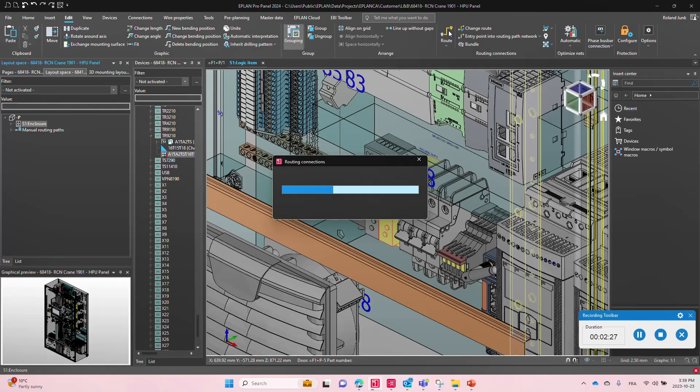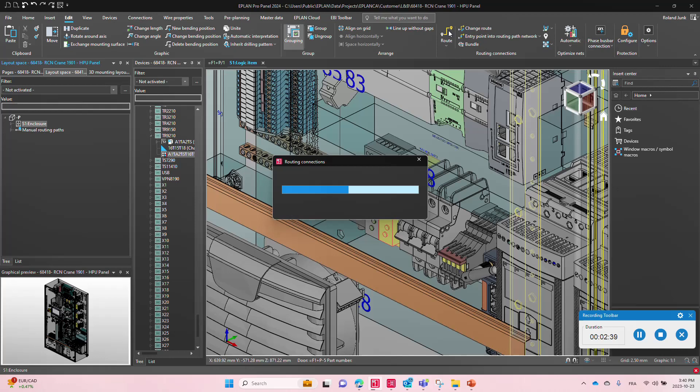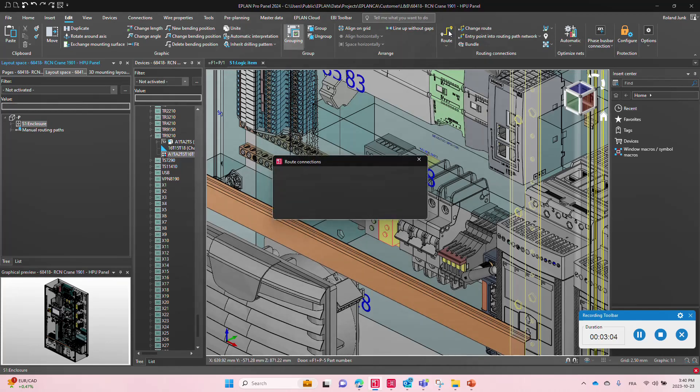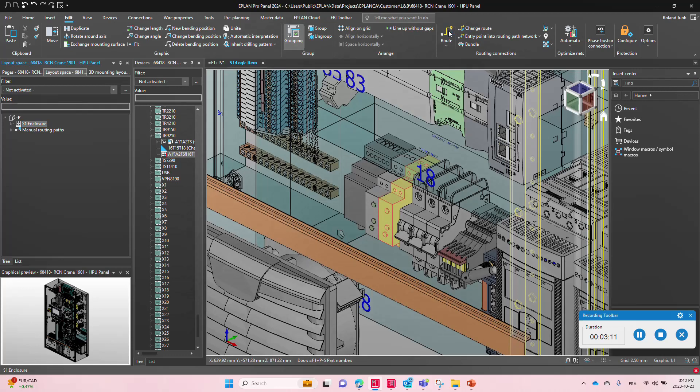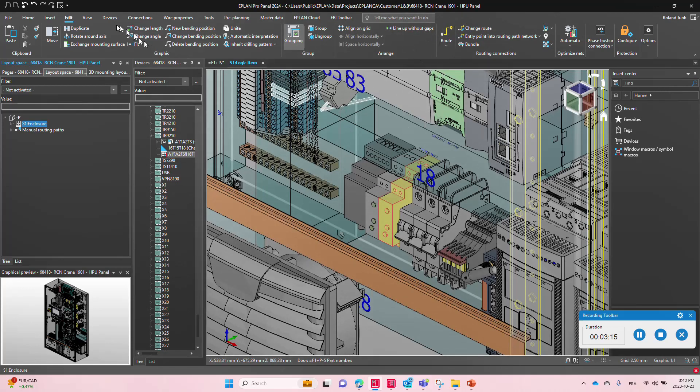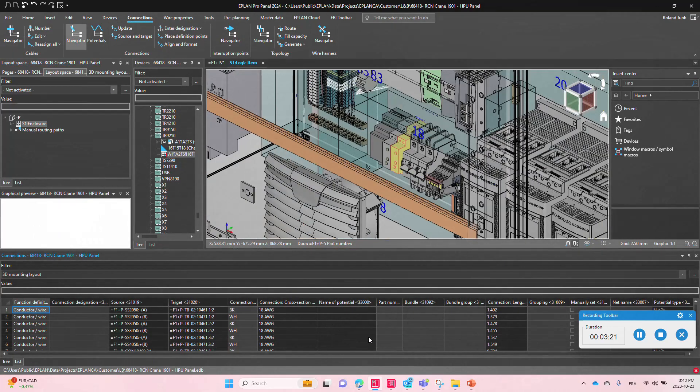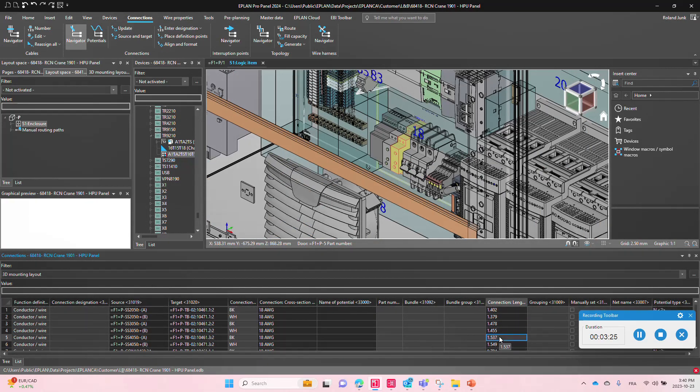So how do I get wire information inside this project to actually be displayed and to be calculated in terms of length? Once you have the digital twin, you need information about the wires. Typically you would go into your electrical schematics, place some symbols; they are connected to each other via connections that actually can tell you what wire size, wire gauge, whatever. Here unfortunately in this particular project I have only a few schematic pages and not too many connections. As you can see, we only have a few wires that show up. So most likely if I go here to my connections navigator, I only have a few wires in here, not too many—five or six or seven.